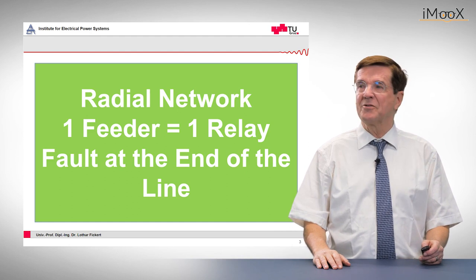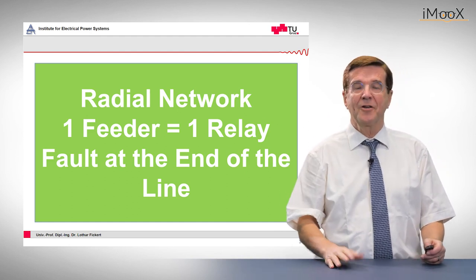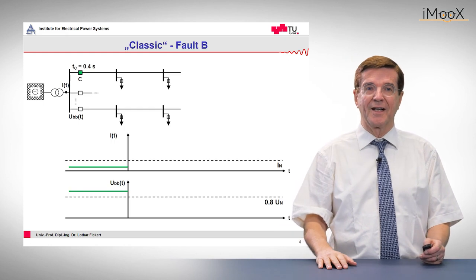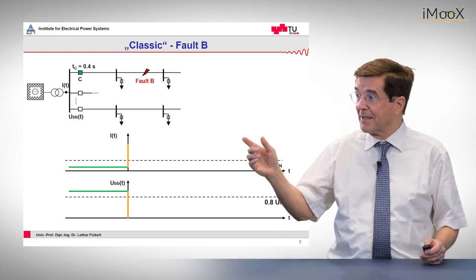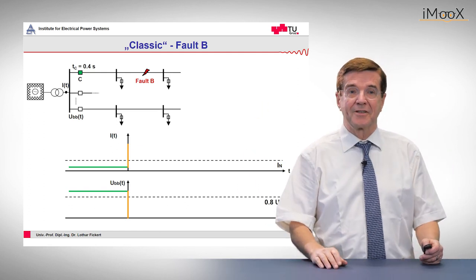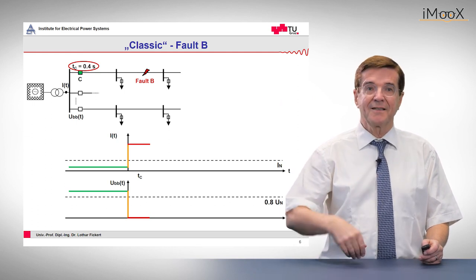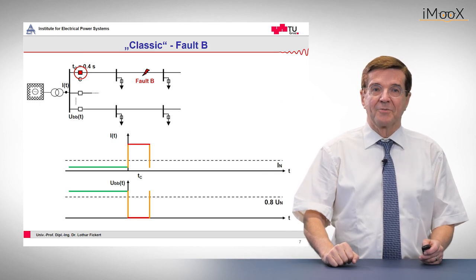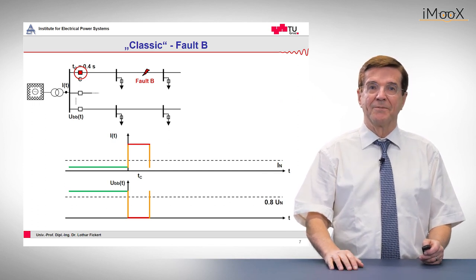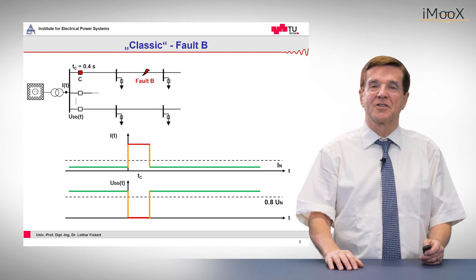Let's start with a very simple radial network where one feeder is protected by one relay and we assume a fault at the end of the line. So we have the network, a fault occurs, and immediately the current goes up and the voltage on the busbar drops. Then the timer is started. After, for example, 0.4 seconds, the circuit breaker is opened and we trip.